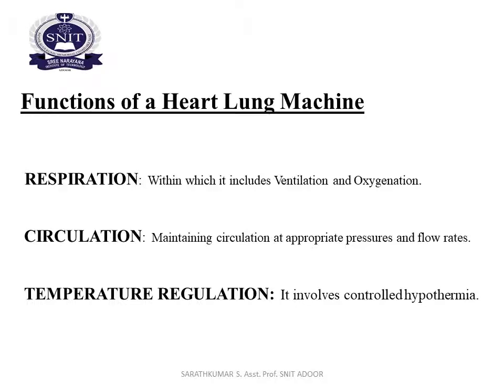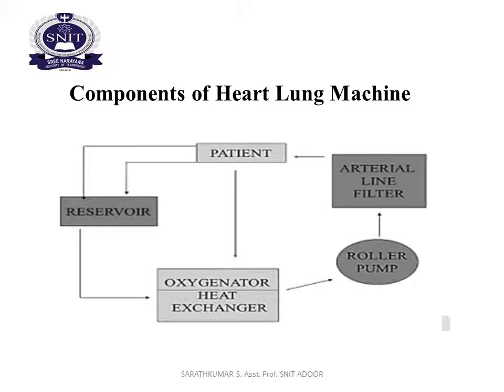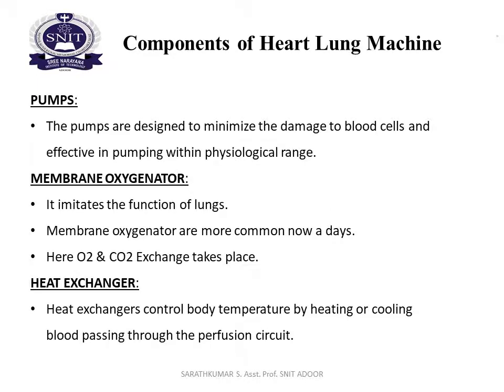The different components of a heart lung machine include a membrane oxygenator, arterial line filter, and roller pump. The pump is designed to minimize damage to blood cells while effectively pumping blood within the physiological range. The membrane oxygenator imitates the function of the lungs.